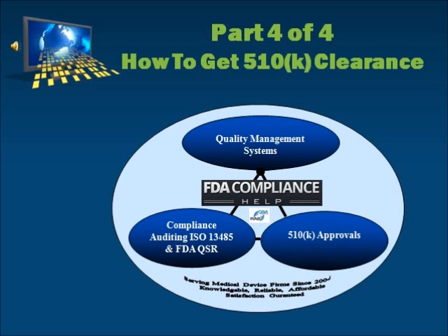You have a choice of submitting your 510K in the traditional format, or using the globally harmonized format abbreviated STED. If you are interested in using the STED alternative, see the FDA guidance entitled, "A Pilot Program to Evaluate a Proposed Globally Harmonized Alternative for Pre-Market Procedures." We will focus on the traditional format.